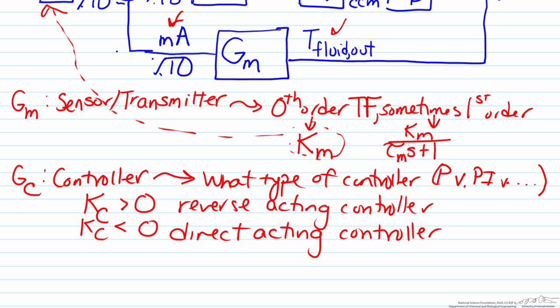So when KC is greater than zero, it is known as a reverse acting controller. When KC is less than zero, that is known as a direct acting controller. You can get some more information about reverse versus direct acting controllers using other screencasts.